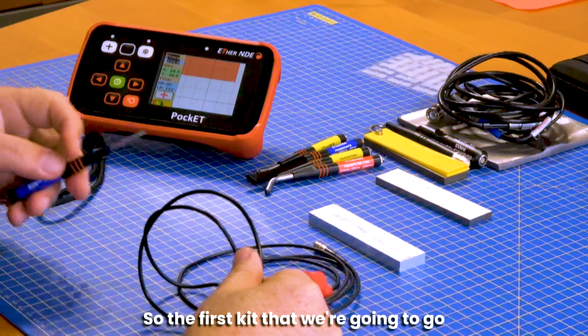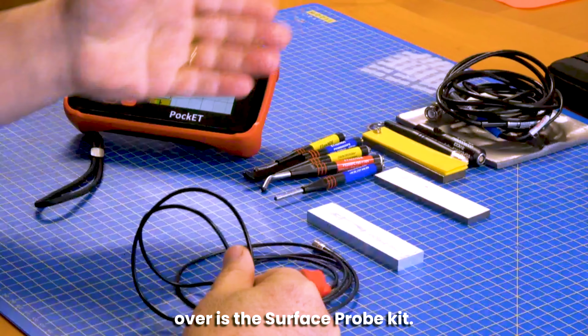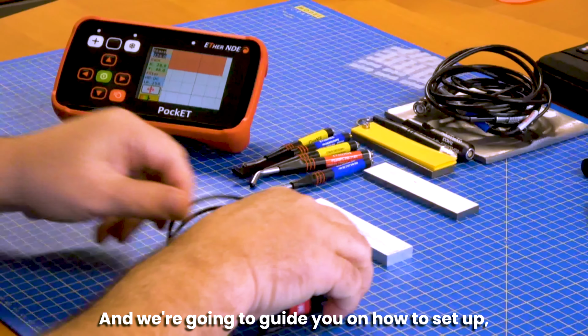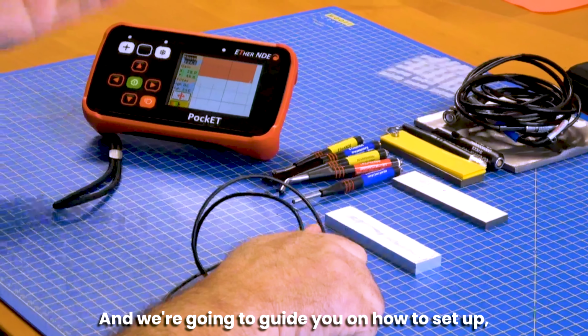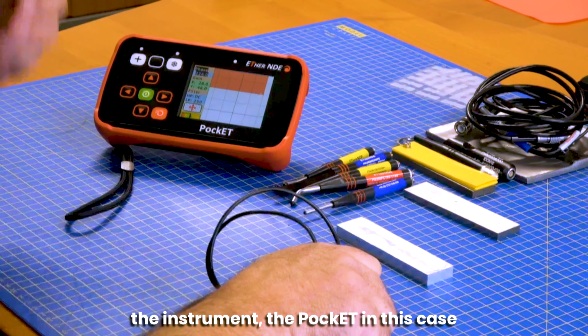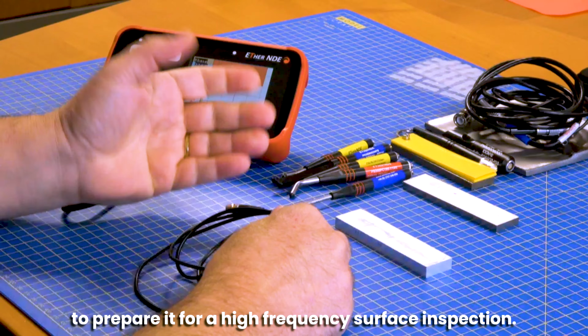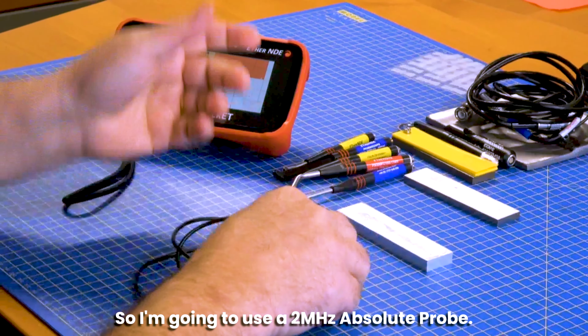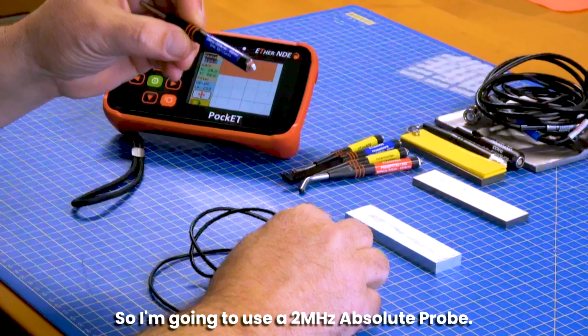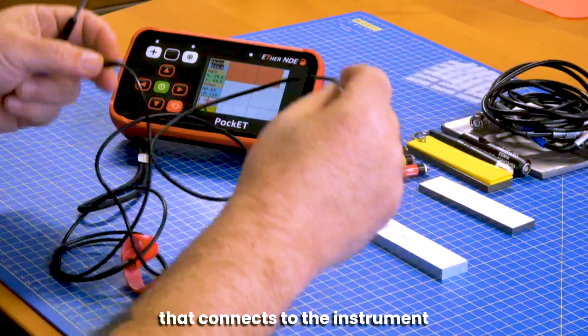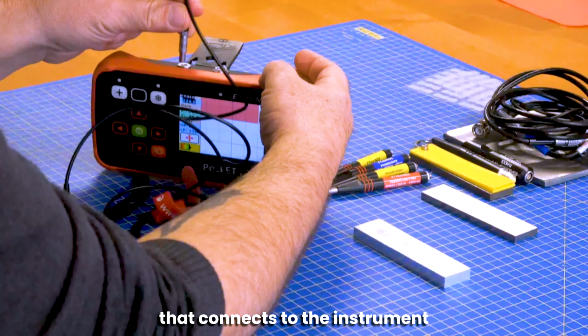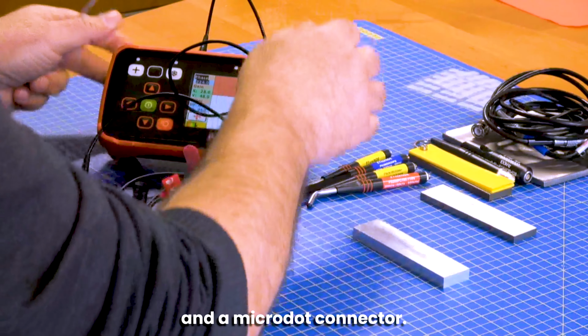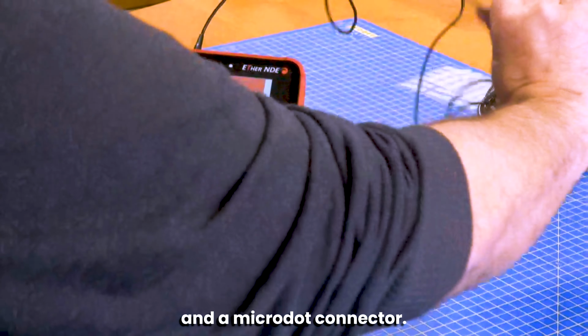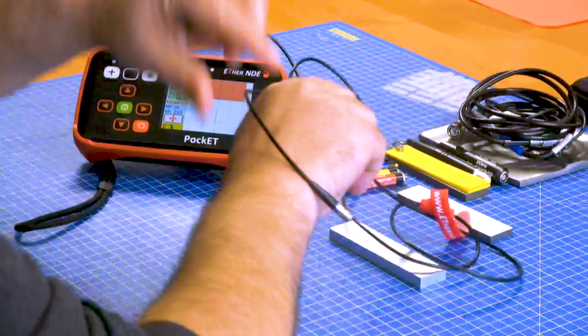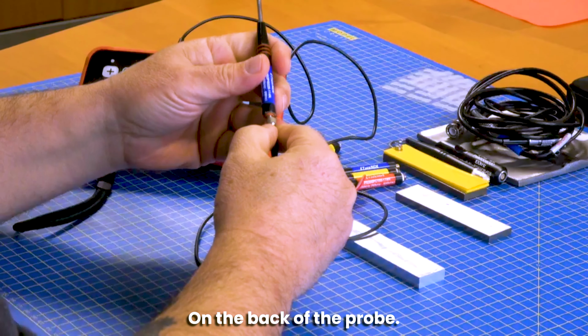So the first kit that we're going to go over is the surface probe kit, and we're going to guide you on how to set up the instrument, the PockET in this case, to prepare it for a high frequency surface inspection. So I'm going to use a 2 megahertz absolute probe. I have a lead that connects to the instrument and a micro dot connector on the back of the probe.